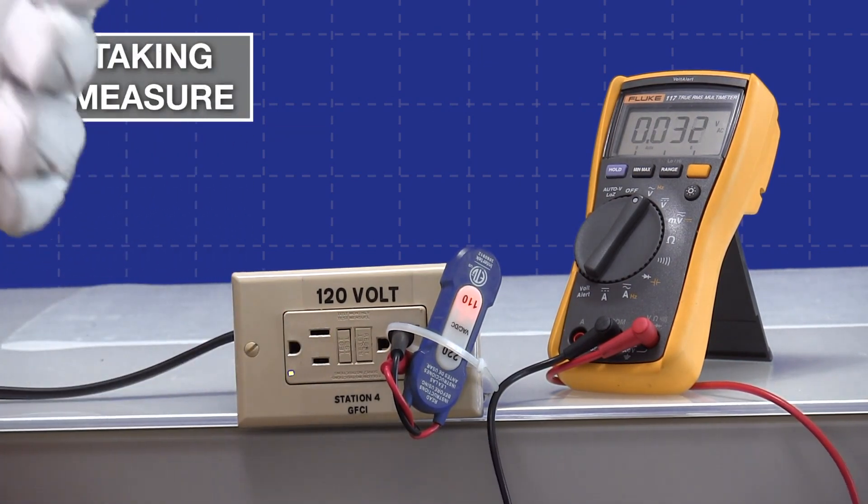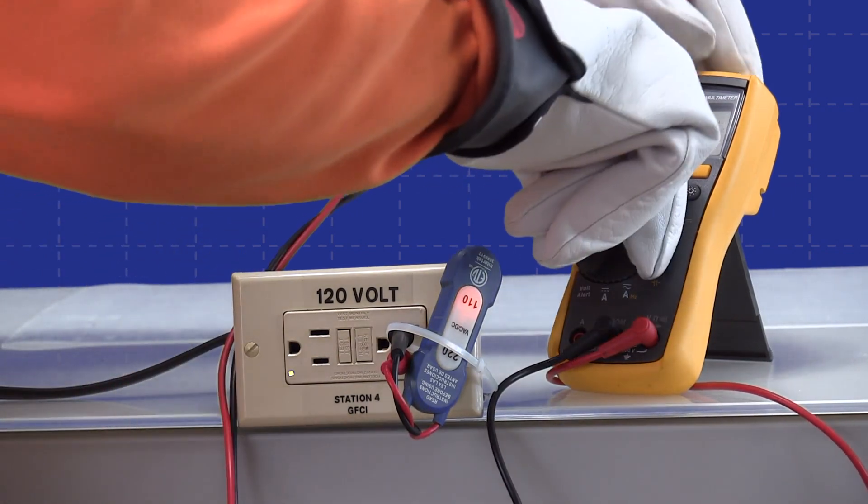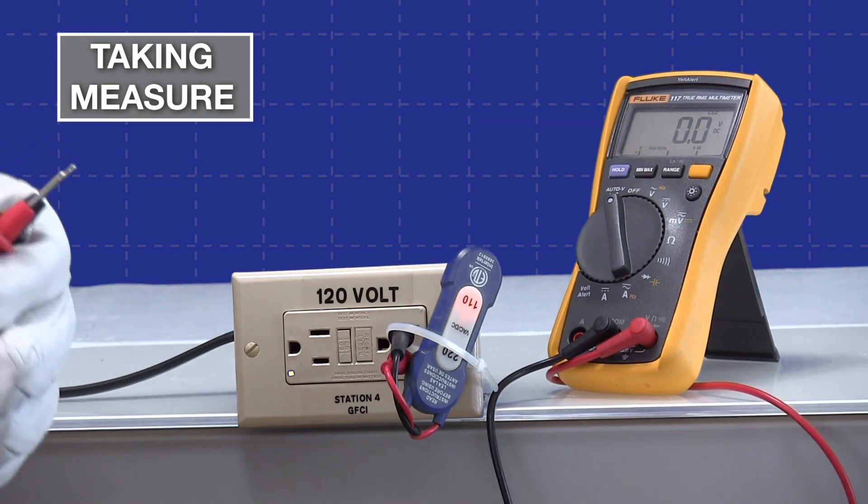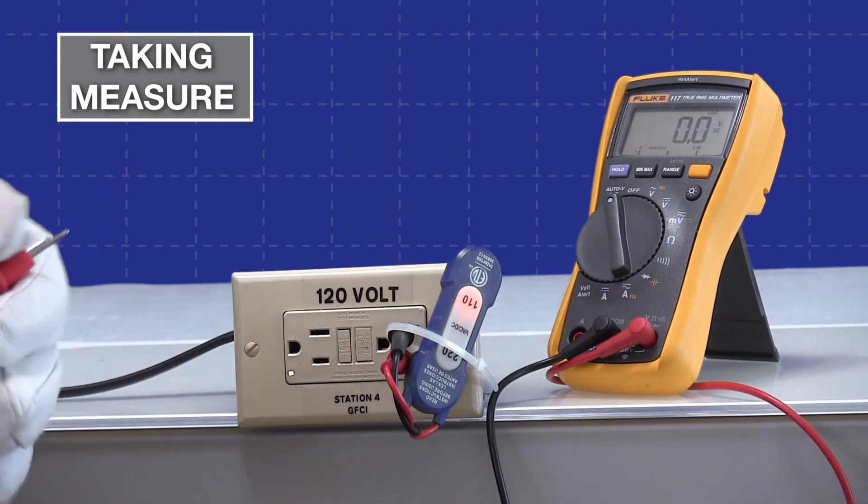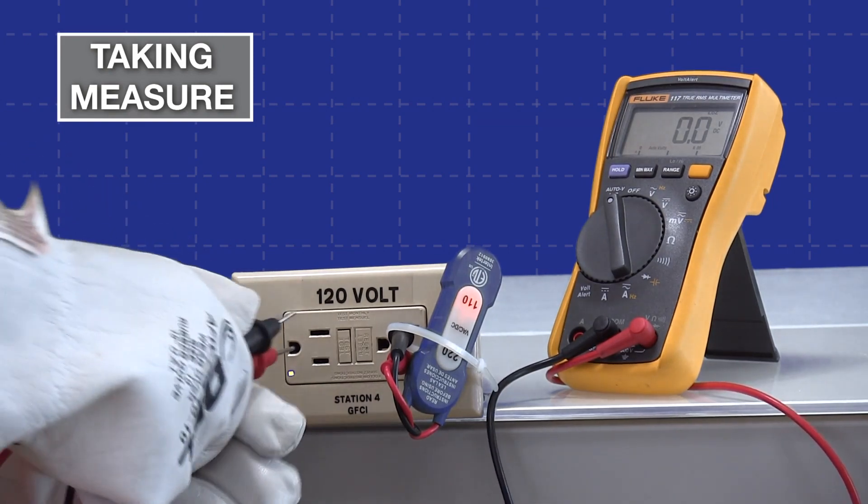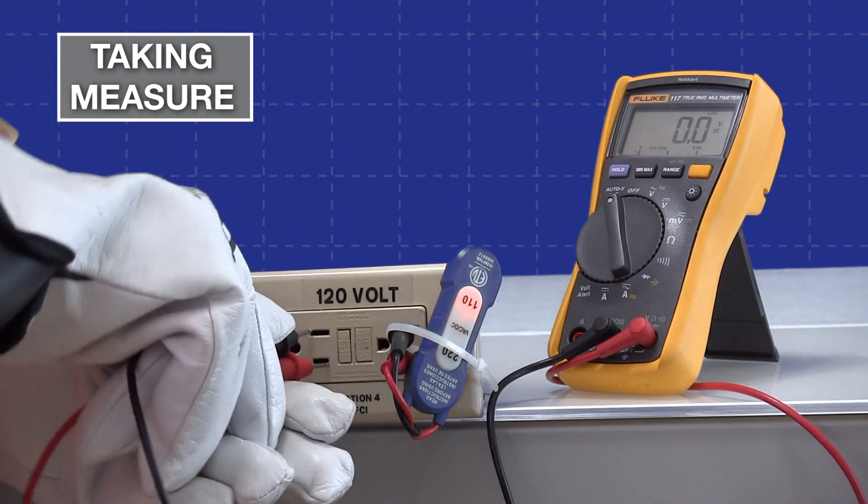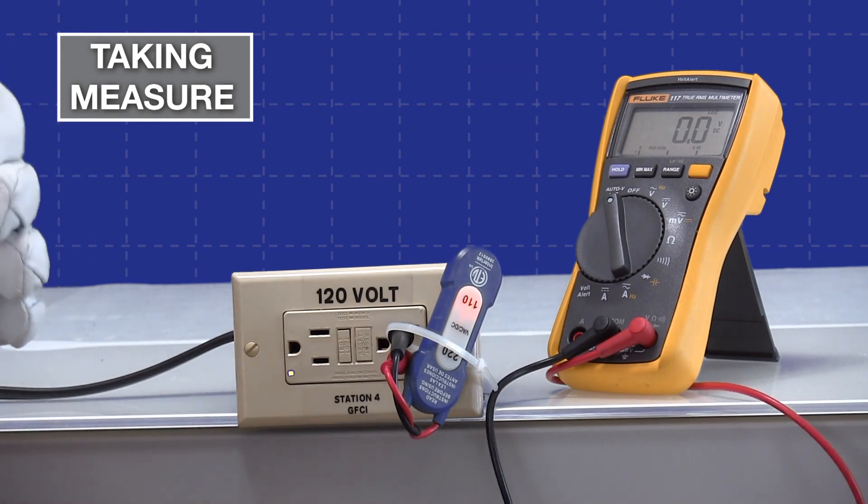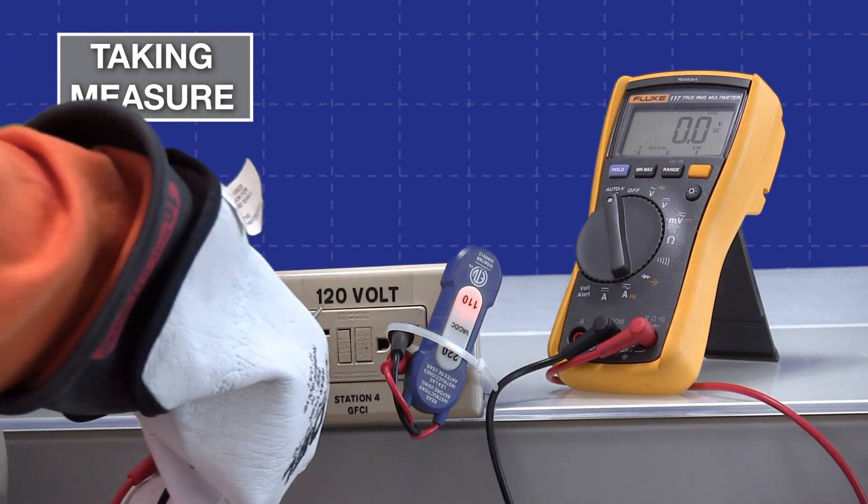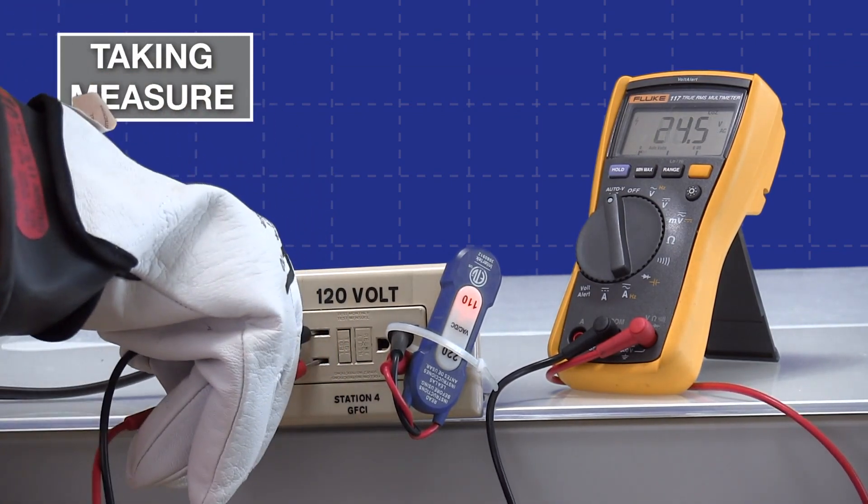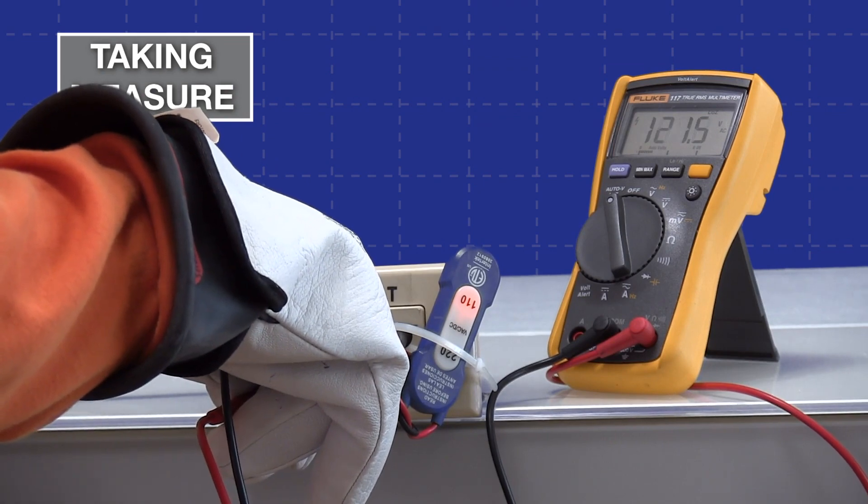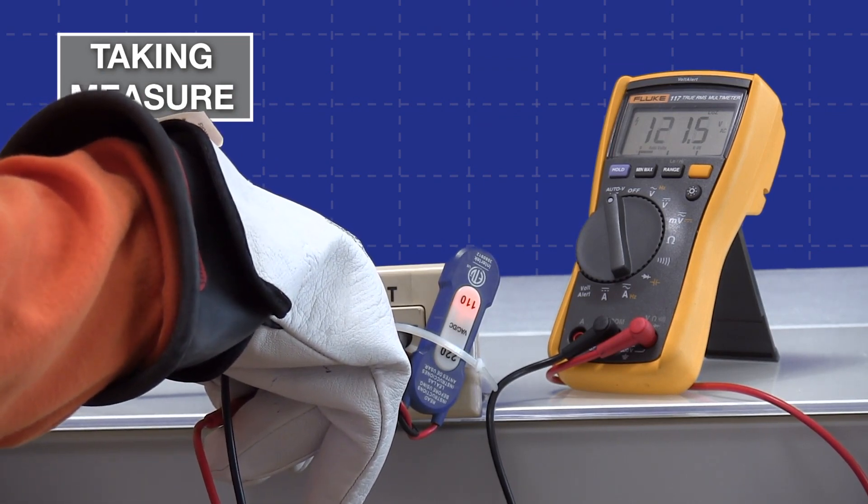Now, I'm going to switch to the low impedance input, and that's over here in this position. Now I went to the low impedance instead of the high impedance, and we'll take a measurement of the circuit again under normal conditions. We have 121.5 volts on that. That worked out fine.